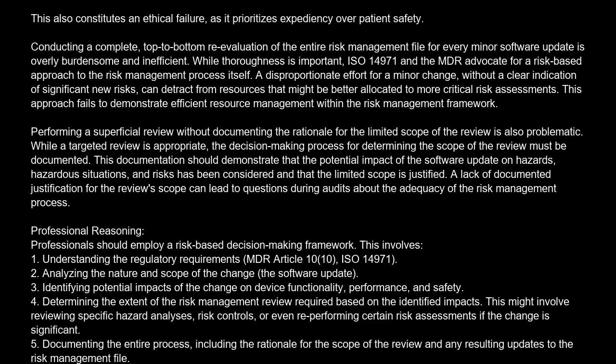This might involve reviewing specific hazard analyses, risk controls, or even reperforming certain risk assessments if the change is significant. 5. Documenting the entire process, including the rationale for the scope of the review and any resulting updates to the risk management file. This systematic approach ensures compliance, patient safety, and efficient use of resources.